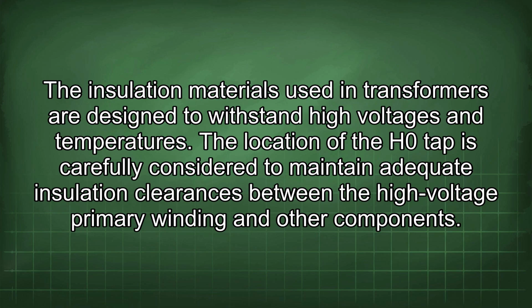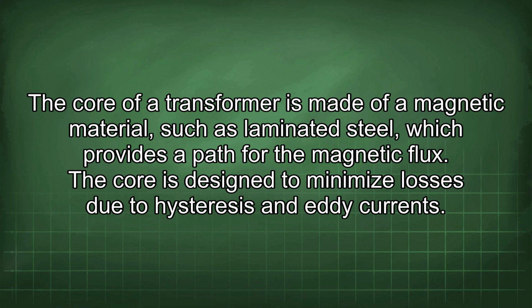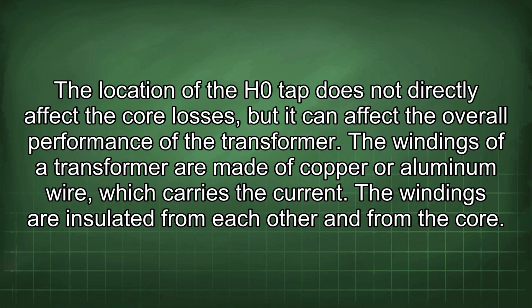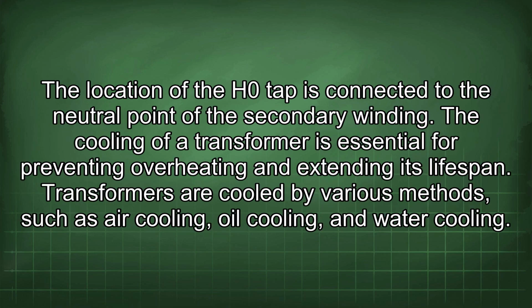and other components. The core of a transformer is made of a magnetic material such as laminated steel, which provides a path for the magnetic flux. The core is designed to minimize losses due to hysteresis and eddy currents. The location of the H0 tap does not directly affect the core losses, but it can affect the overall performance of the transformer. The windings of a transformer are made of copper or aluminum wire, which carries the current. The windings are insulated from each other and from the core. The location of the H0 tap is connected to the neutral point of the secondary winding.